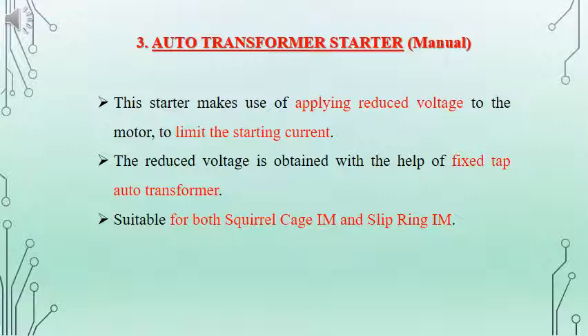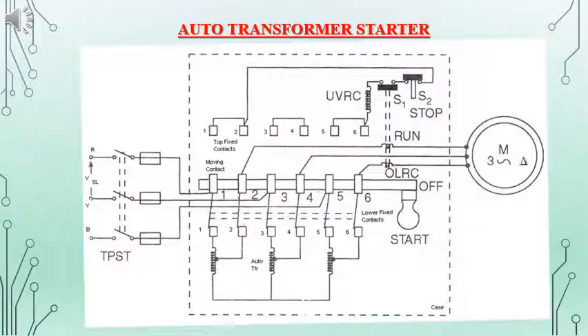And here we will be using a fixed tap auto transformer. It can be used for both squirrel cage as well as slip ring induction motor. Here we have the circuit diagram for the auto transformer starter. We have a set of lower fixed contacts as well as top fixed contacts. They are numbered from 1 to 6 at the top and the bottom. There is a moving contact mechanism too. There are two positions, that is start and run condition.